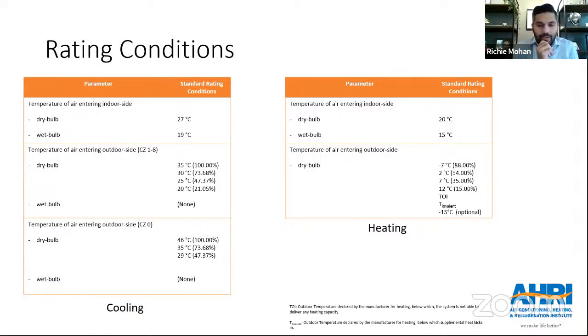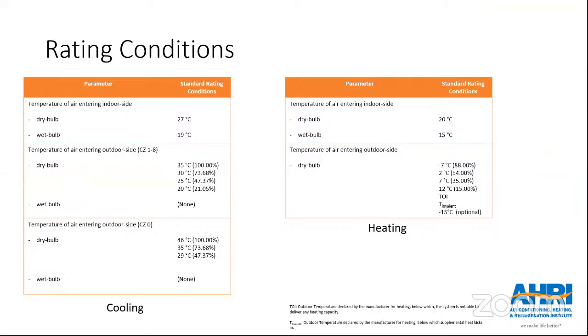I think that has to be addressed at the global standard level. We did add the wet bulb on the indoor side, but on the outdoor side we need to have a discussion as to whether we need a wet bulb temperature or not. It's going to make a large difference on the performance of the unit, since the energy consumption pattern changes with higher humidity levels. This could be misleading in areas with high humidity. For example, at 35 degrees dry bulb with a small wet bulb temperature, machines are going to perform better versus somewhere else. So incorporating wet bulb temperature is critical when evaluating the performance or rating of these machines.